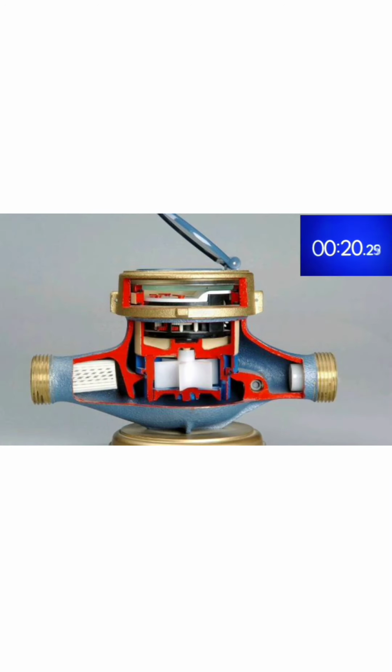Problems related to velocity water meters. Velocity water meters can register air flows, which will lead to over-registration of consumption, especially in systems with intermittent supply, when water supply is re-established and the incoming water pushes air through the meters.